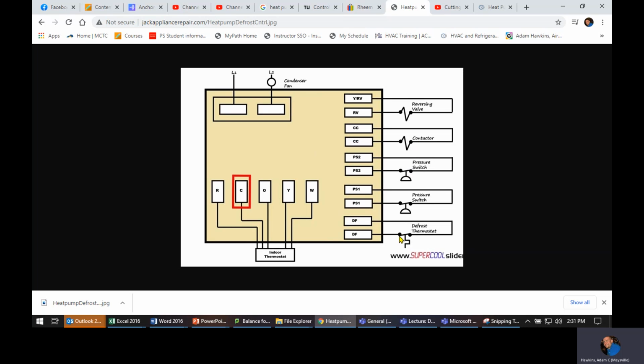According to your book, it says the defrost thermostat usually closes below 30 degrees and opens between 50 and 70, depending on system design. So at about 30 degrees, that stat is going to close. It may stay closed the whole time, but that unit's not going to go into defrost until it times out. So it's going to wait that preset amount of minutes until it checks to see if it needs defrost.